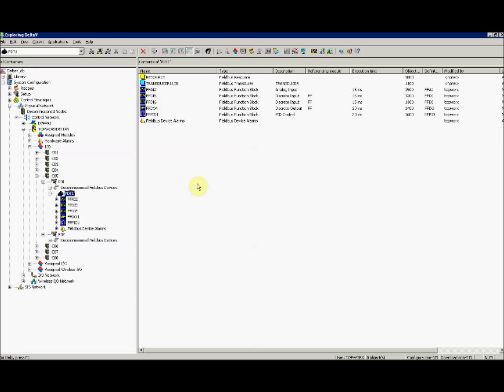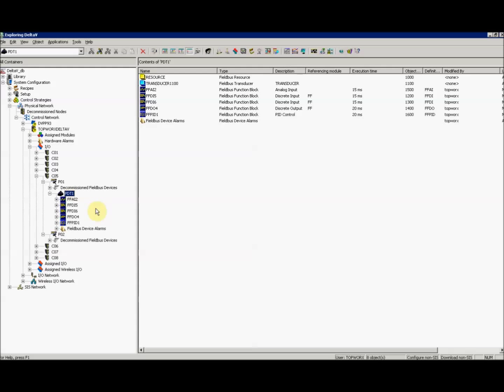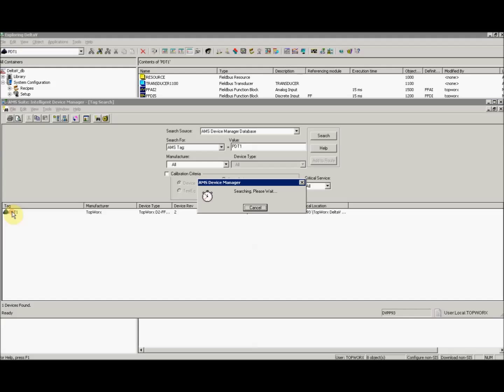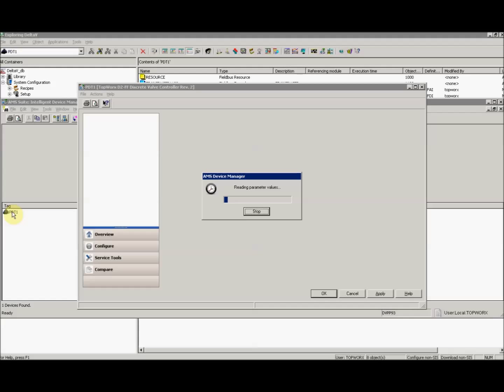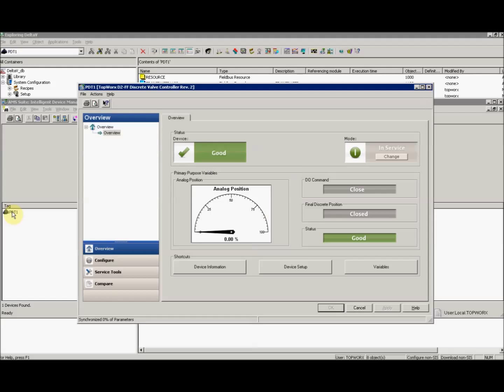To calibrate the device, there are a few different methods. You can do it locally with the button board by removing the lid to the device. You can do it with an Emerson 375 or 475 handheld, or you can also do it through AMS in DeltaV. To start off in AMS, right-click on your commissioned device and select Open with AMS Device Manager. Select the unit from the list. And click Device Setup.